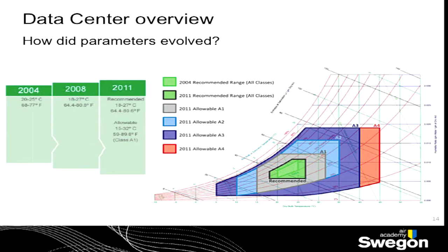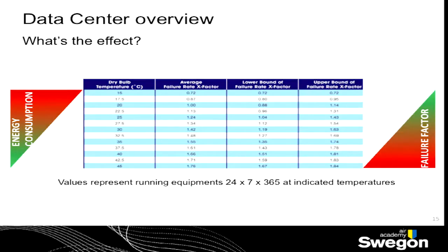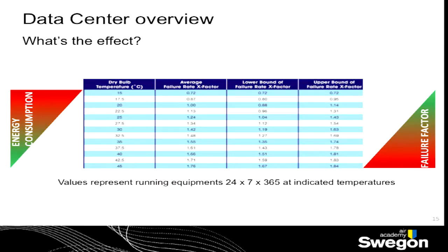What does it mean, recommended temperatures? We have to consider it from 2 different points of view. Because increasing the temperature means that we are increasing the average failure factor. But increasing the temperature also means that we are saving energy. So we have to find the best compromise between these 2 situations. But what does it mean that the failure factor increases? For example, if we look at the allowed temperature, 18 to 27, okay, so it means from here, more or less, to here. The average failure factor goes from 0.9, let's say, to 1.3.